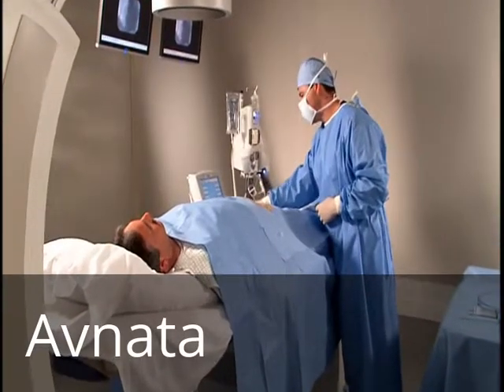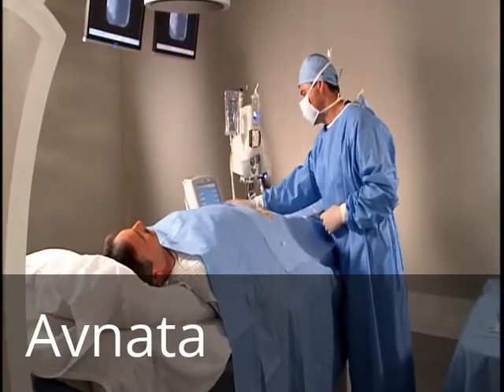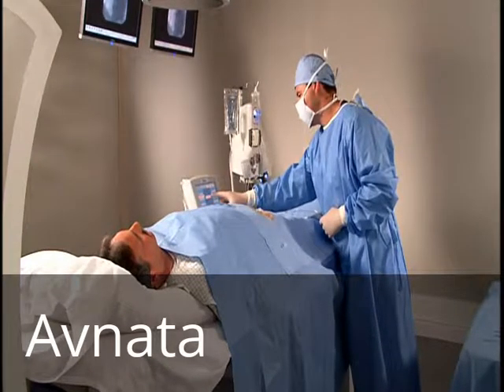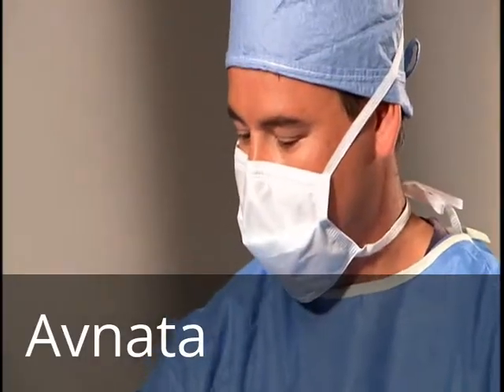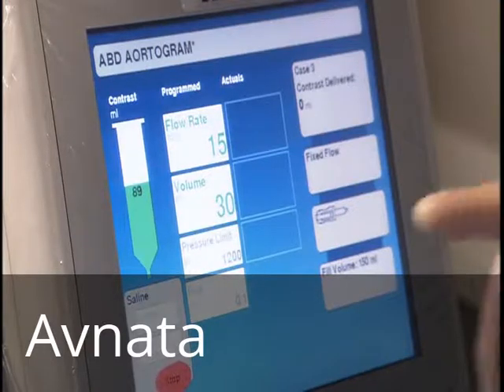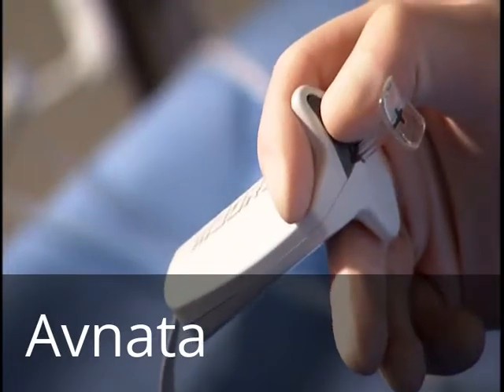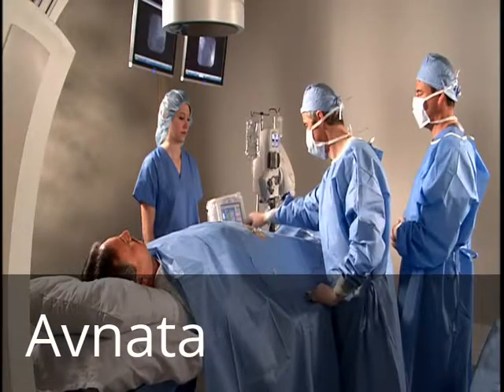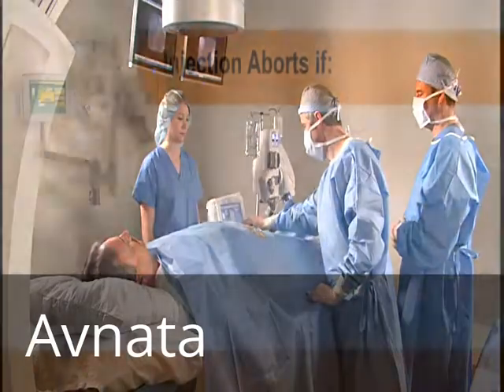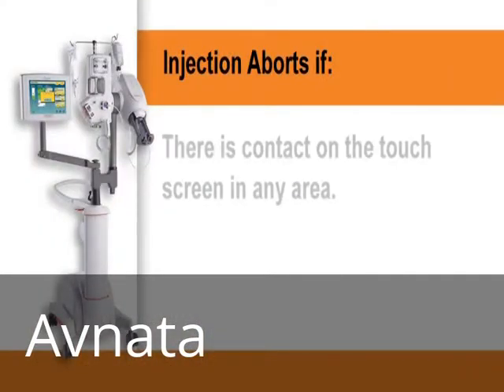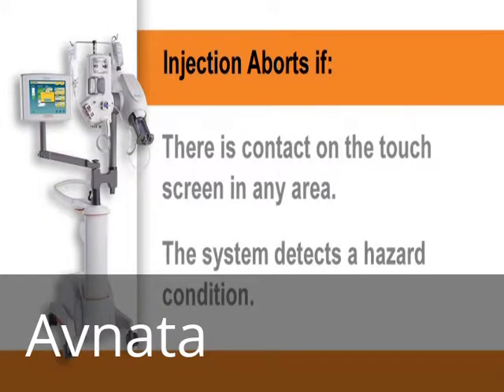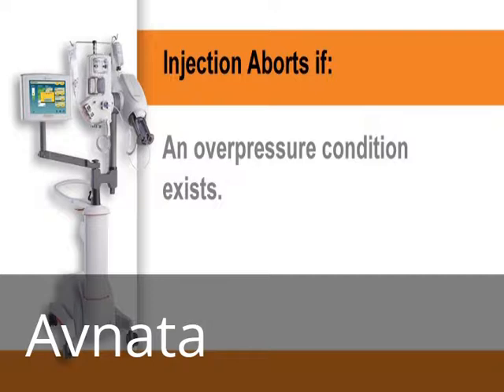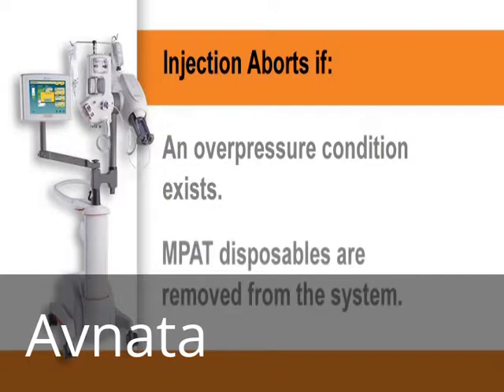ASF is not available when the system is filling the syringe, armed for contrast injection, or when contrast is actively being delivered. The operator can stop ASF at any time by touching Stop on the screen or the hand controller saline button. Note: additional safety features are incorporated into the system. The injection will abort if there is contact on the touch screen in any area when injecting, the system detects a hazard condition, an overpressure condition exists, or if MPAT disposables are removed from the system.